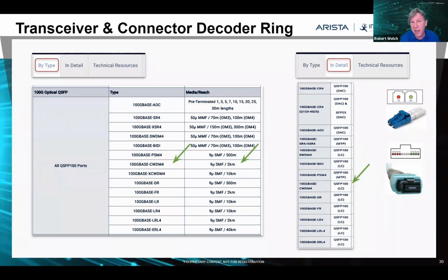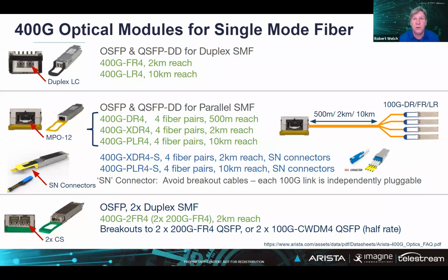I like the AOCs better than the DACs because if they're too long, you can coil them up a bit and tuck them away, whereas DAC cables, not so much. The other thing with DAC is, even though it runs at a lower wattage because it's going electrical to electrical, not optical, even though it runs at a good speed, like 100 gig and 400 gig, your distance is going to be limited. Also, the bend radius is not great. So if you need to close that door in the front, don't buy a DAC cable. I prefer to use AOC cables, quite frankly. And hopefully this is stuff from a facility perspective where you guys are going, yep, that's exactly what we do.